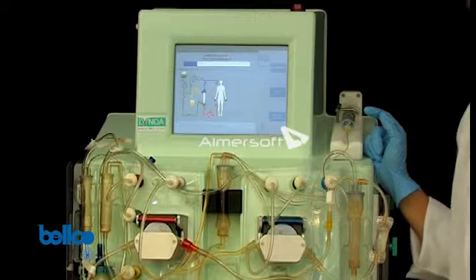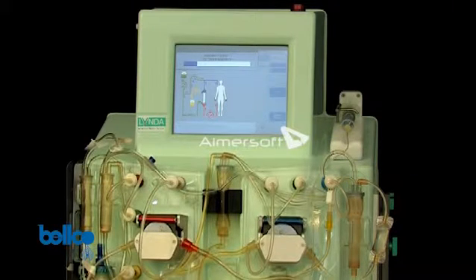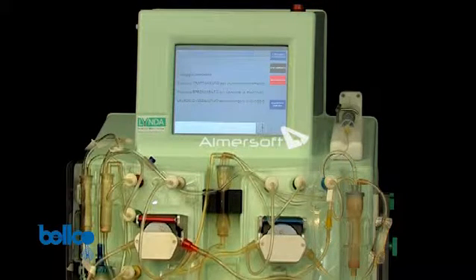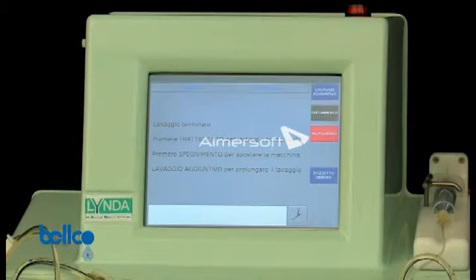During priming, the machine runs all the necessary tests to best prepare the device. In the Cpfa treatment, rinsing lasts about 30 minutes and the device is rinsed with 4 liters of infusion fluid. This is the page displayed at the end of priming.